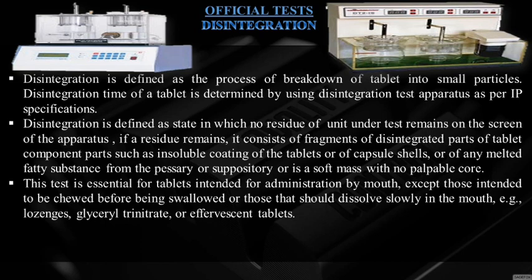The disintegration test is essential for tablets intended for oral administration, except those intended to be chewed before swallowing, or those that dissolve slowly in the mouth such as lozenges, glyceryl trinitrate, or effervescent tablets. The disintegration test does not apply to chewable tablets, effervescent tablets, or slow-dissolving tablets like lozenges or glyceryl trinitrate.